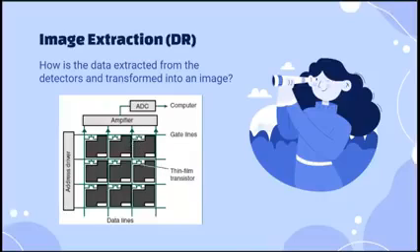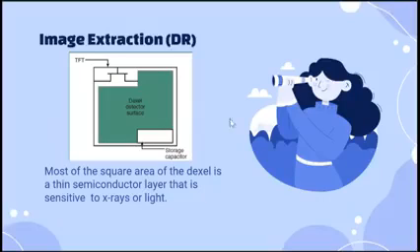It can be 4 by 4, 11 by 11, and so on and so forth. Okay, so going back, this area here, the Dexel detector surface, is the capture area for detecting radiation. So the larger the area as a percentage of the whole square, the more efficient the Dexel will be in absorbing X-rays or light. So the larger the area here, the more absorption will occur.